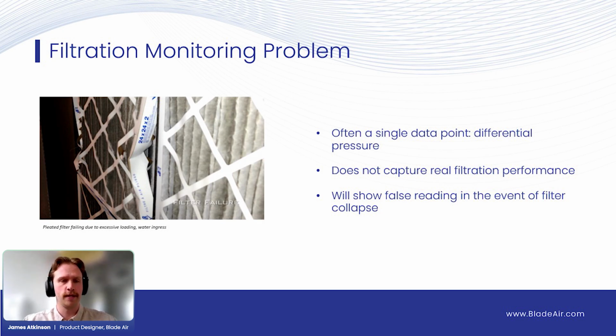So what can happen, let's say you have a filter alarm set that it will trigger an alarm in your system to tell you your filters are dirty if they pass 1 inch of static pressure loss. But if you actually see this picture here, this is a filter that has completely failed. It's broken because the pressure drop got so high and maybe it got moist, but the cardboard has folded and now air is going right through your filter. And now you have no pressure drop. But your system won't tell you that because you're not measuring really your filtration performance, right? You have no filtration in that system. Air is going right through your filter.